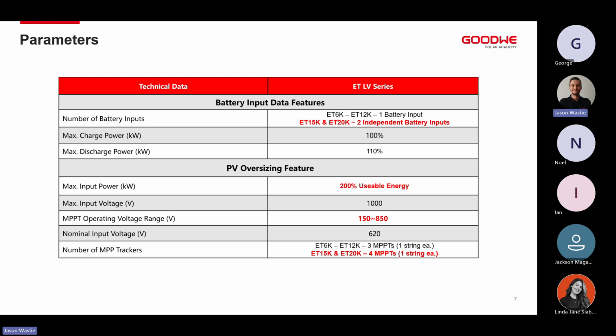So those two independent battery inputs allow us to add on two completely different battery banks together and let them operate completely independently as well. So what that means is we can put 20 kilowatt hours of our Lynx AG3 battery, which is a 5 kilowatt hour battery, on input 1, and we can put 5 kilowatt hours of a BYD battery on the second battery input and have them operate completely independently from one another. We can have old batteries on one input, we can have new batteries on the other input, so it does help for expandability at a later stage.